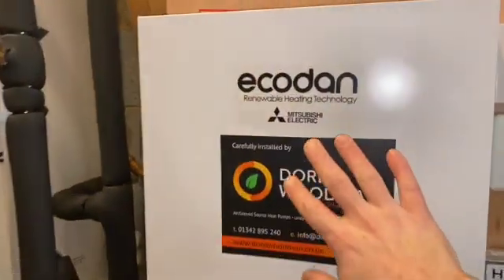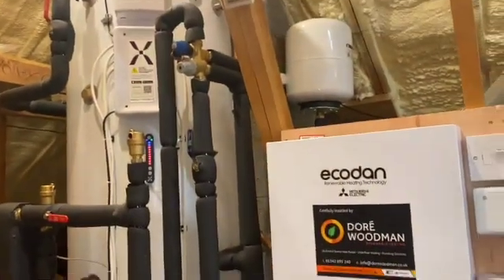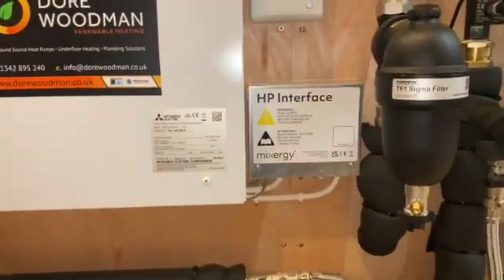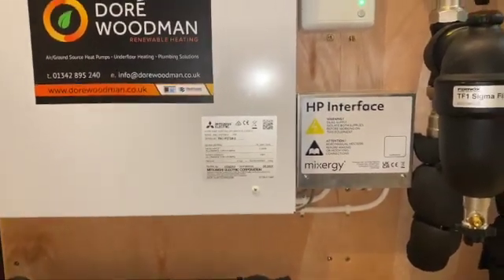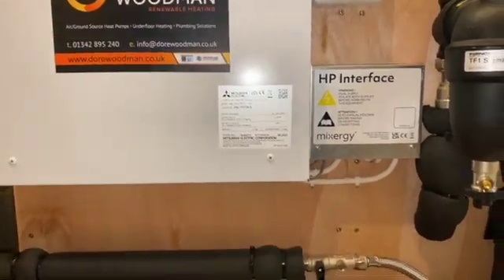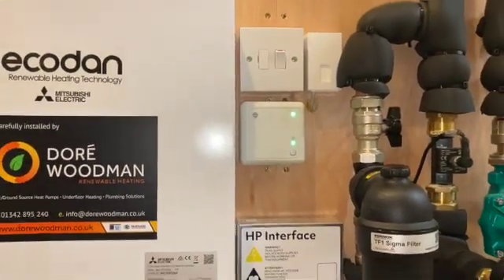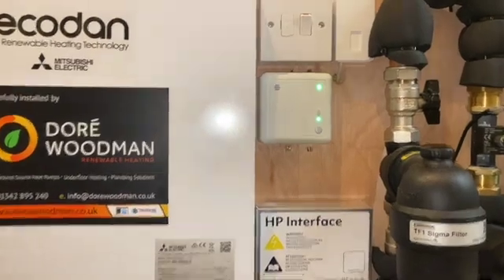With the Ecodan we've got our interface here — this is the controls unit that talks to the heat pump and interacts with the interface for the Mixergy cylinder. Inside there are various dip switches and, depending on the heat pump manufacturer, you can select which one you're using. Different systems use different methods of communication and hot water charging, so the Mixergy team have come up with configurations for each individual heat pump manufacturer to work effectively with their system. The customer also has Hive, which they've always used, so the heating thermostat control is managed via the Hive app.